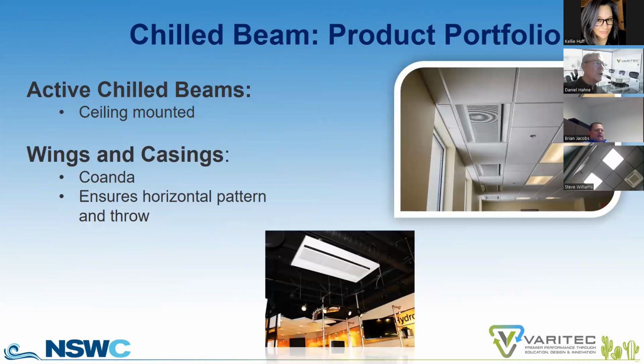If you have an active chill beam mounted in an upper level of a room that has no ceiling, it's just free hanging and exposed, you'll want to provide what are called Coanda wings in casings. Coanda wings are extended flanges along the length of the beam that allow the air discharged from the beam to establish what is called Coanda, which means that it hugs the surface and is discharged further into a room to create more efficient mixing within the space.